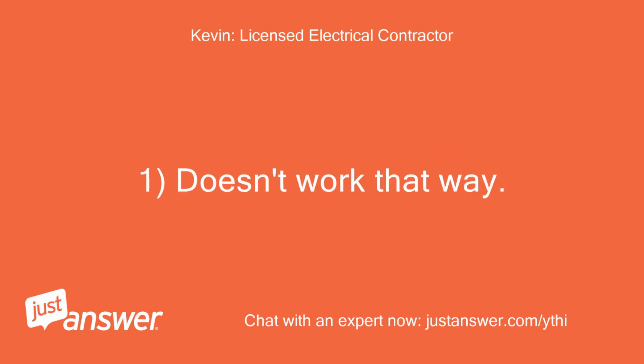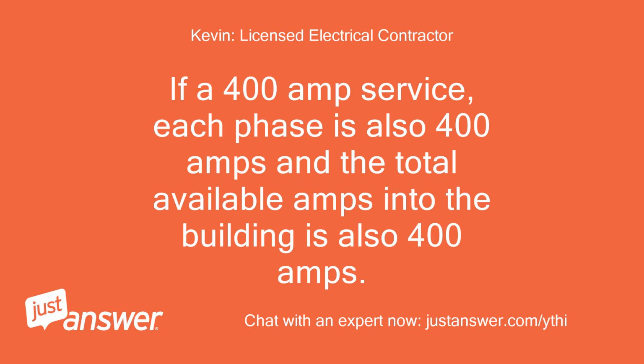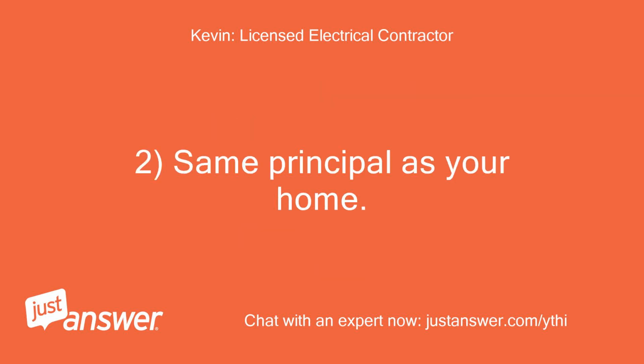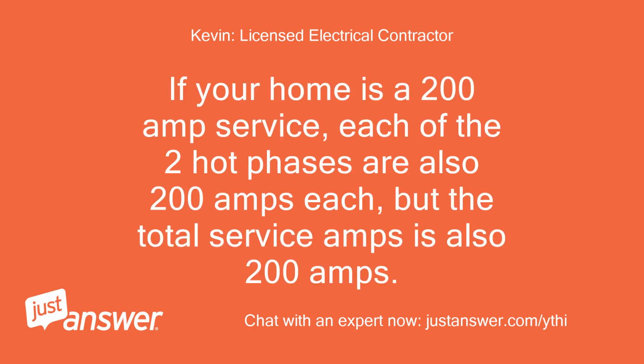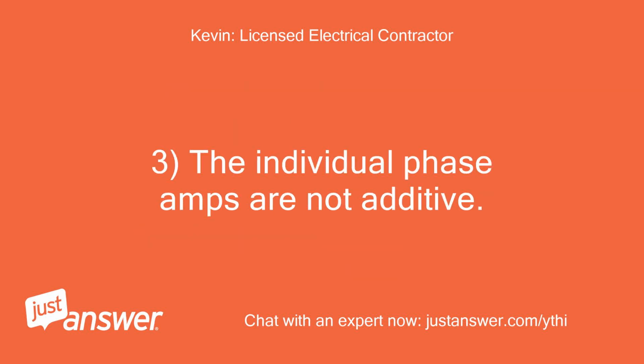1. Doesn't work that way. If a 400 amp service, each phase is also 400 amps and the total available amps into the building is also 400 amps. 2. Same principle as your home. If your home is a 200 amp service, each of the 2 hot phases are also 200 amps each, but the total service amps is also 200 amps. 3. The individual phase amps are not additive.